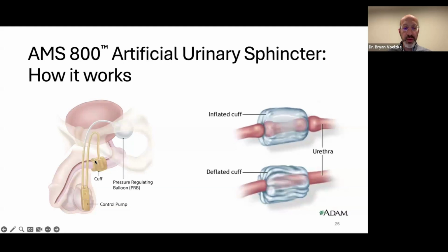But what happens is fluid exits the cuff, goes into the control pump, and then goes to the balloon. And then gradually over 30 to 40 seconds, the fluid cycles back out, back through the control pump, goes back into the cuff, and then closes back off. And you can see here, this is just showing when the cuff inflates, the urethra, which is the red tubular structure, is compressed. When it's deflated, the red tubular structure is open and you're able to empty your bladder.